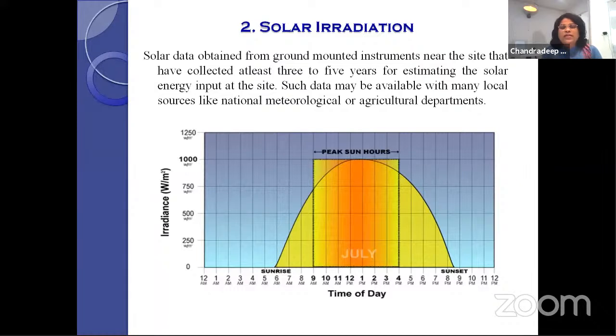So while calculating the capacity of the solar module for a solar water pump or solar power plant or any solar electrical application, not thermal, you should take into consideration peak sunshine hours. Your IMD, Indian Meteorological Department, gives you the sunshine hours, not peak sunshine hours. So as a solar engineer, we take into account the PSH while calculating the capacity of the power plant or module array for the solar water pump.